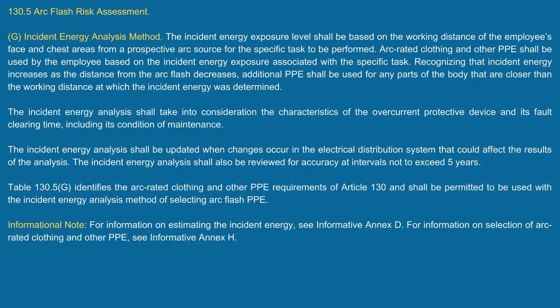Then look what it says here. The incident energy analysis shall be updated whenever changes occur in the electrical distribution system that could affect the results of the analysis, and this incident energy analysis shall also be reviewed for accuracy at intervals not to exceed 5 years.